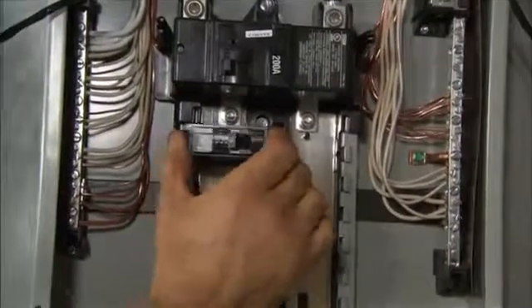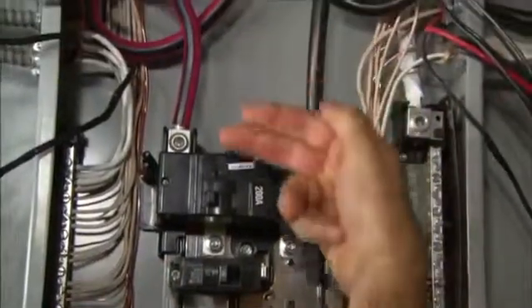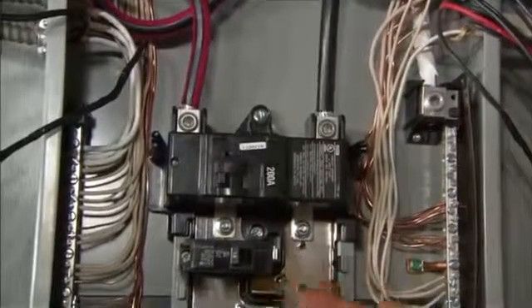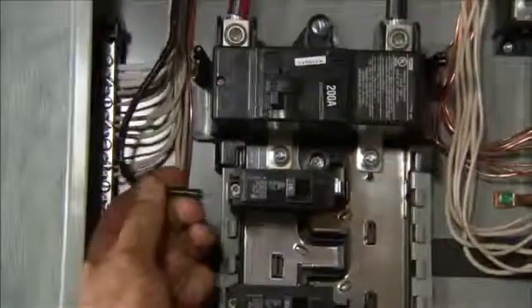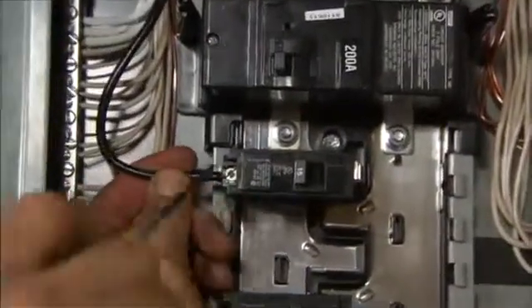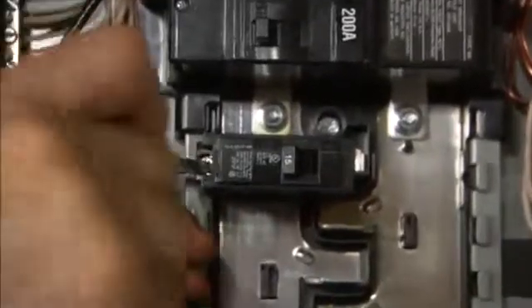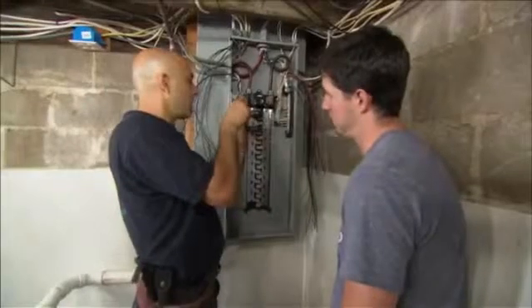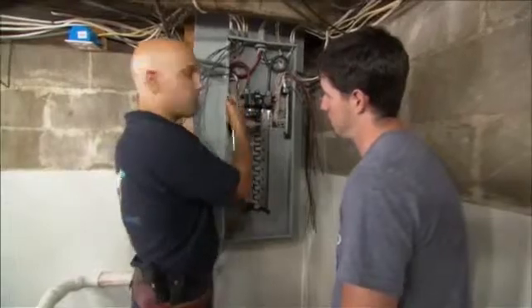Now when I plug it in, it's going to receive 120 volts from the left side of the bus bar. This wire here is a 15 amp wire. I'm going to go ahead and install it. Tighten it down, and that's going to send power right up to that circuit.